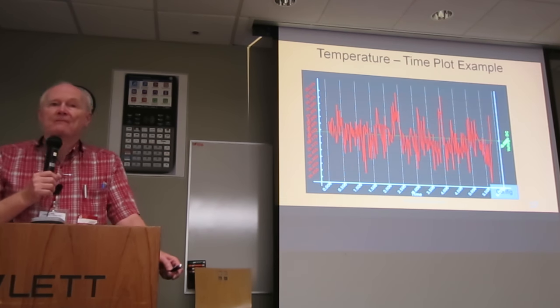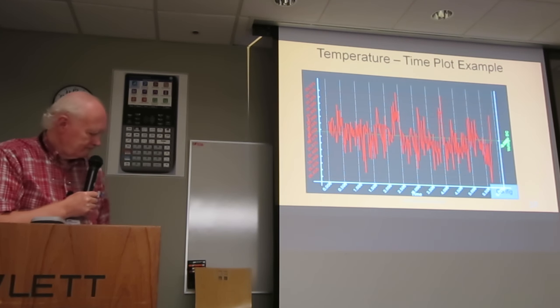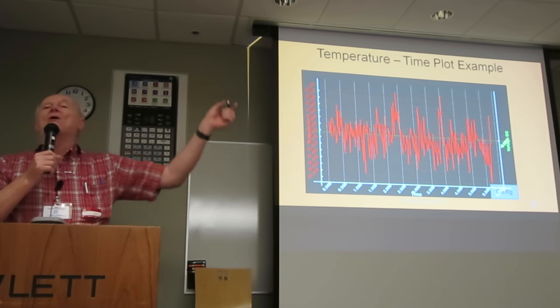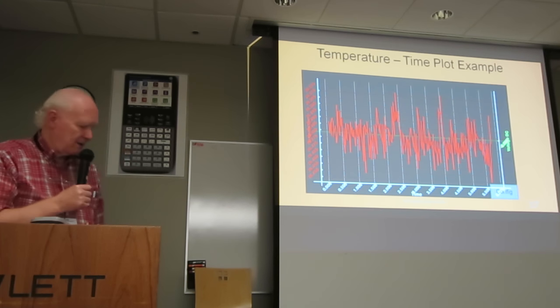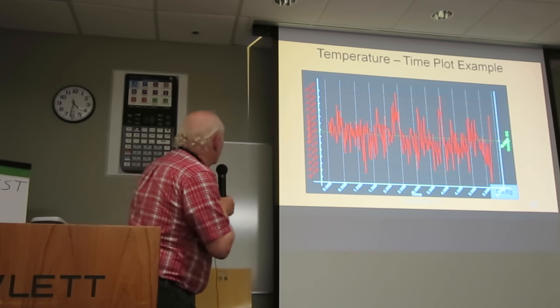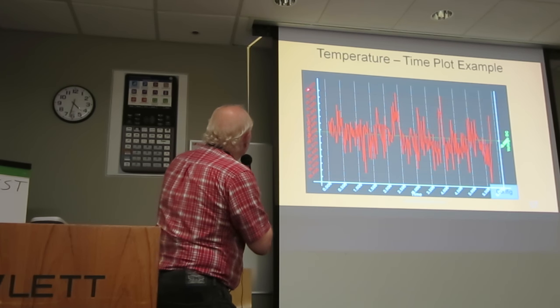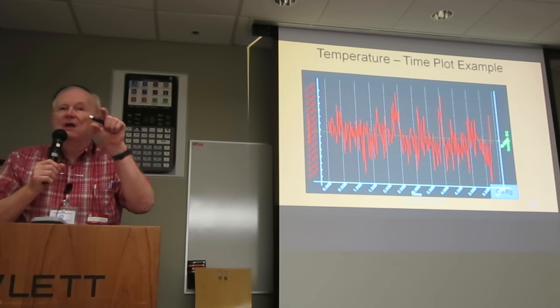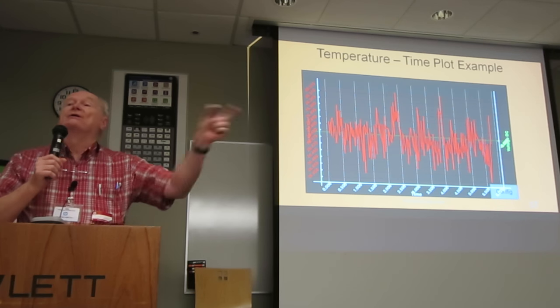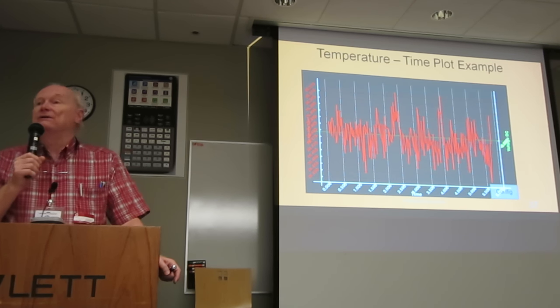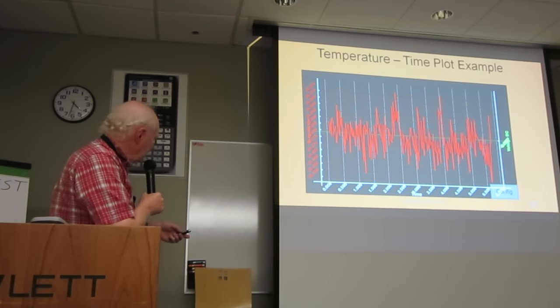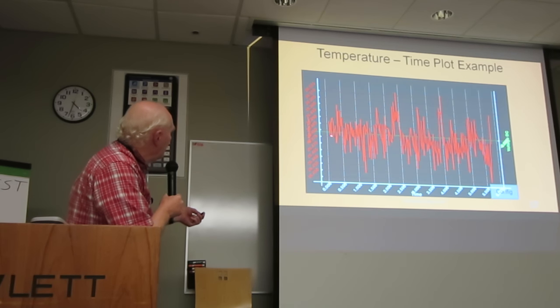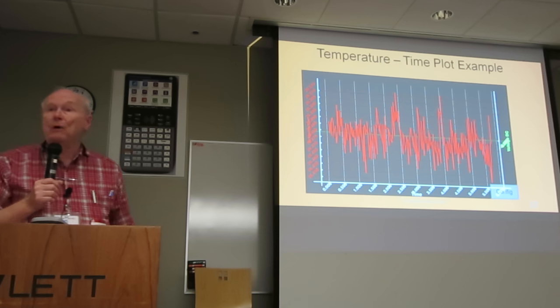Here's an example of a temperature-time plot. One of the issues with this instrument is that because of its high resolution, it gives you all kinds of digits — it's overloading you with data. You can see here we're going from 26.450 degrees up to 26.513 degrees — that's the resolution for you. If you're measuring to that resolution, any instability or change you're going to see. The time axis shows 0, 0.5, 1.0, 1.5 seconds — in half a second we've got 10 or 12 changes in temperature, but we're able to capture all of that.